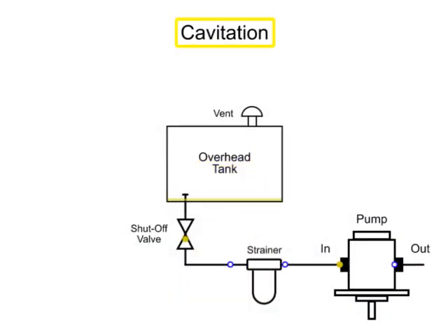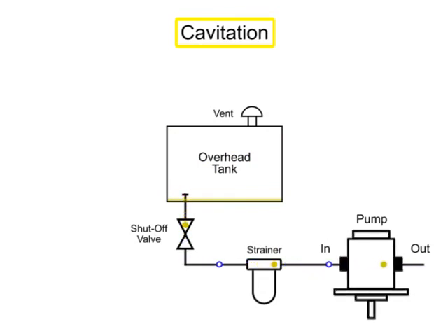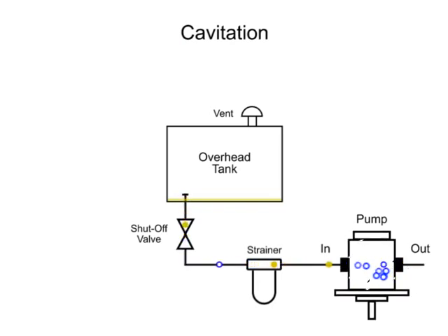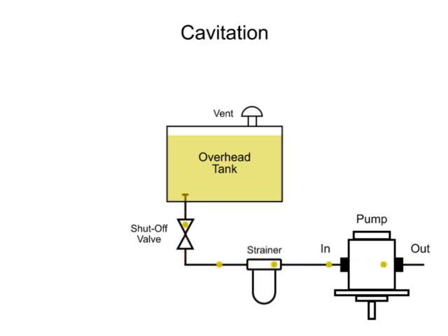Cavitation is often characterized by loud noises such as grinding or as if there are marbles in the pump, and pitting damage to parts as material is removed by the bubbles. If fluid systems are properly designed and properly maintained to prevent dirt or air entering the system, operation will be efficient and reliable.